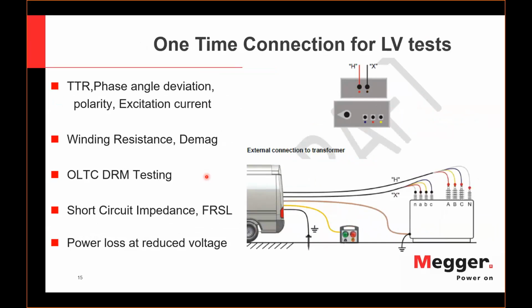Same principle is organized on the low voltage side. Here we also strive for one-time connection. And here, this time, we remove the short and we connect each bushing with an individual Kelvin clamp, 4 clamps on the HV side and 4 clamps on the LV side, connected to the particular switch box, and organize a TTR test that checks amplitude and phase angle, polarity, excitation current. We can connect a winding resistance meter, make a demag after this process is over, check the condition of a tap changer, record the dynamic oscillograms and compare them between different taps, make a short circuit impedance.